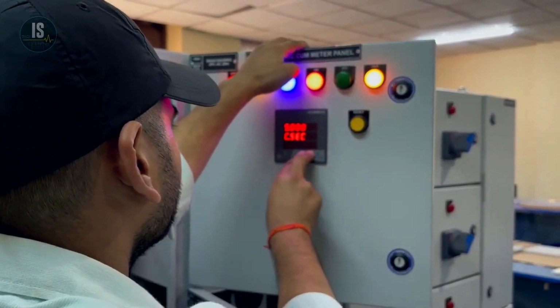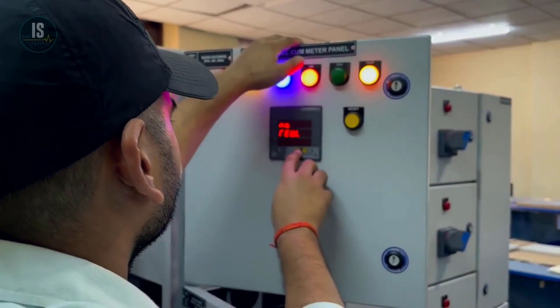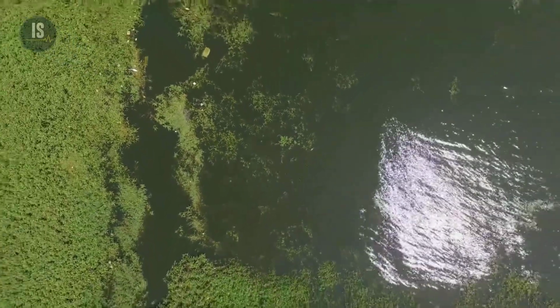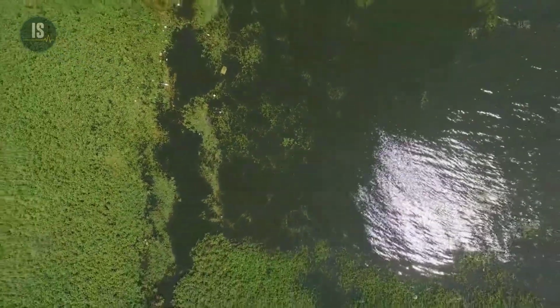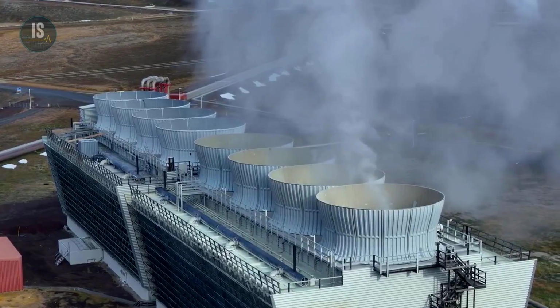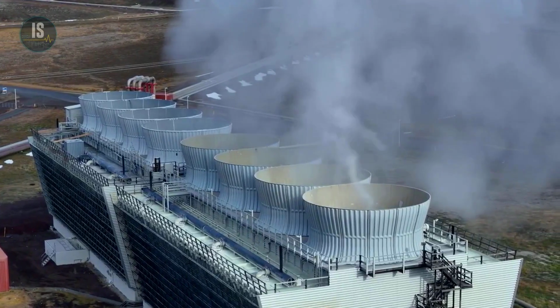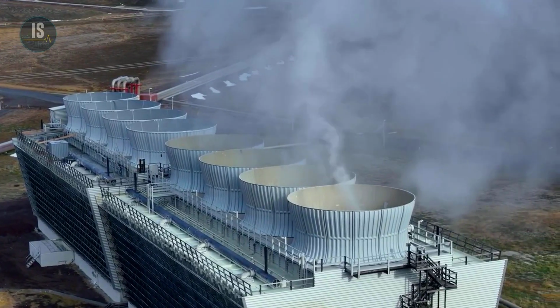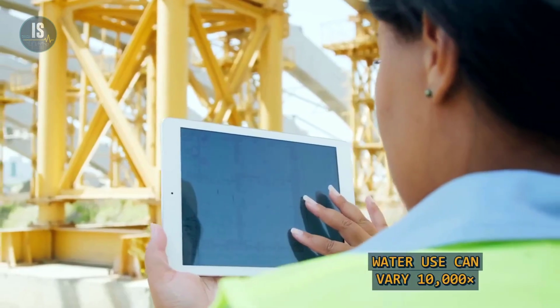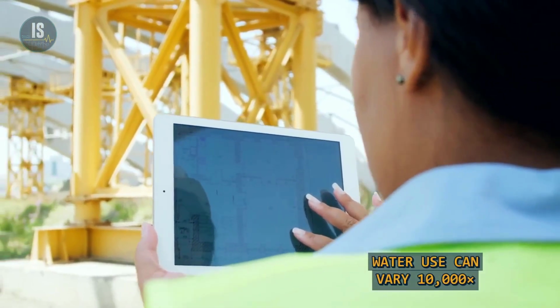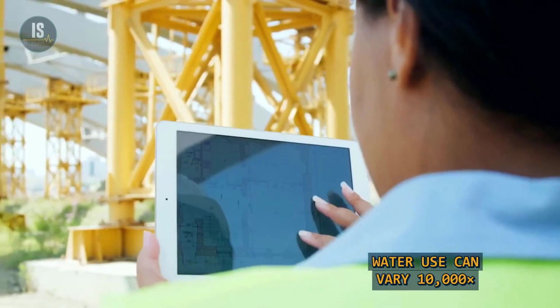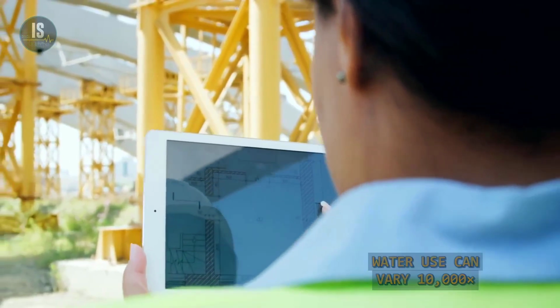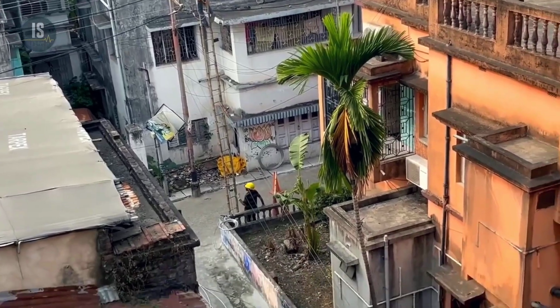This is why 'one AI prompt uses this many liters of water' is usually a bad universal claim. A Lawrence Berkeley study found workload-level water use can vary by more than ten thousand times depending on the server, utilization, grid, climate, and cooling design. The useful conclusion is not one dramatic number. It is that location and engineering choices matter enormously.